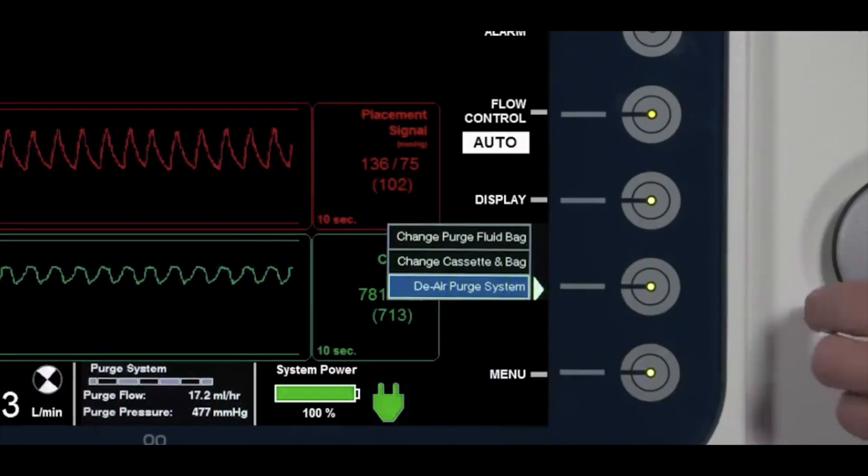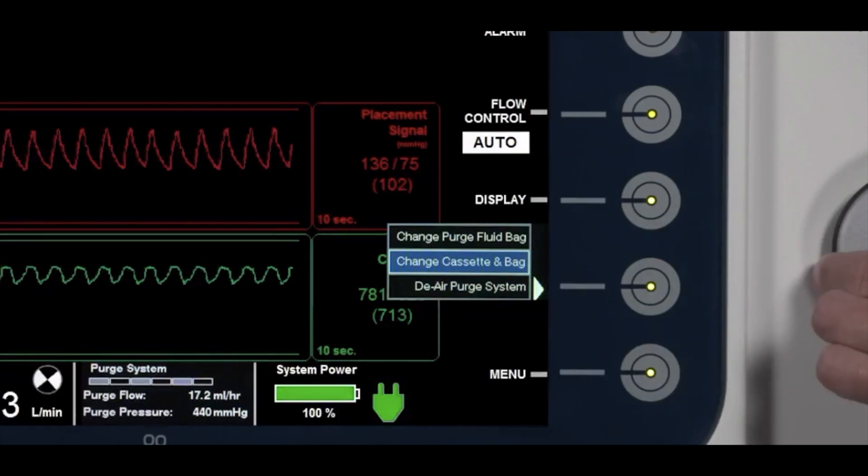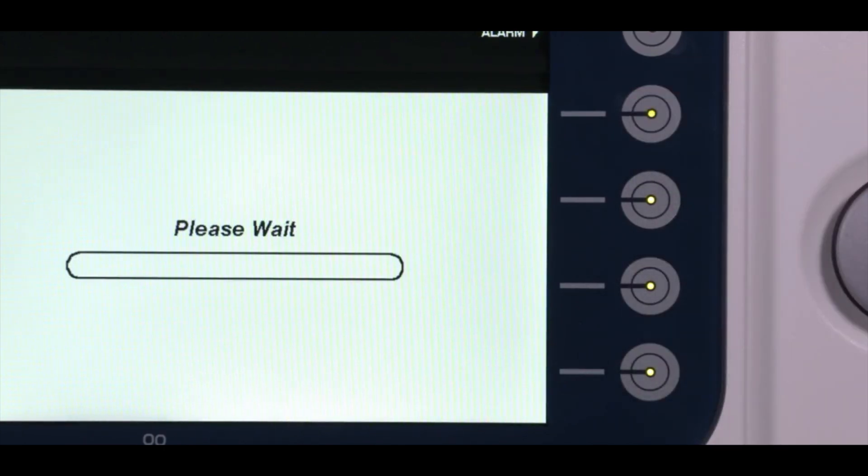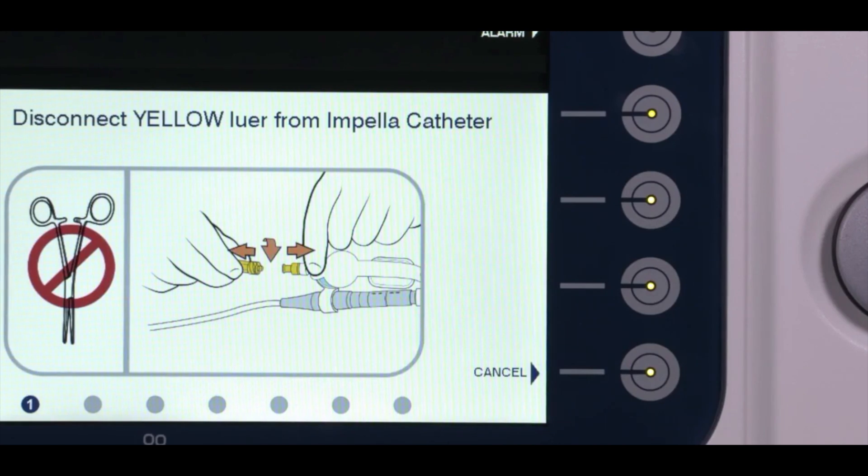How to change the purge fluid: To begin the change cassette and bag procedure, select the purge menu soft button. Use the selector knob to scroll to change cassette and bag and press in on the selector knob. This procedure should be completed within 90 seconds of disconnecting the luer. When reconnecting, a wet-to-wet connection should be made to avoid air entering the system. The supplies needed include a bag of dextrose 5% in water with heparin and a new purge cassette. Press start to begin the procedure. A blue progress bar will appear while the automated Impella controller primes the system, and once completed, the AIC will automatically advance to the next screen.